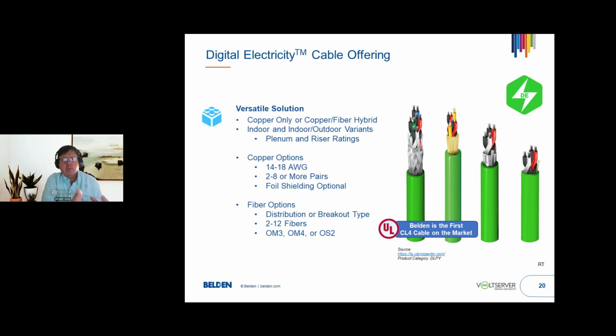As I mentioned before, we worked closely with VoltServer to develop the digital electricity cable. We tried to get every variant they needed to handle virtually all of their applications. All the cables had different shielding — shielded, unshielded, copper only, or hybrid. A hybrid cable has both copper conductors and fibers, so now we can do power and data with one cable pull. Different gauge sizes are needed for the different power requirements.